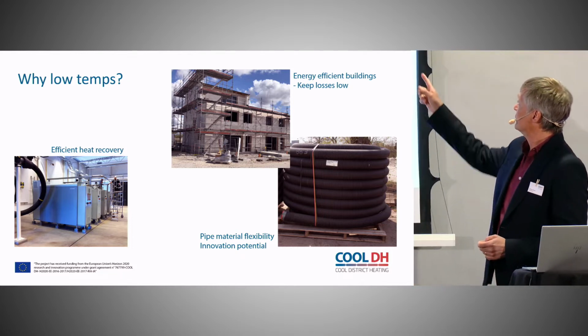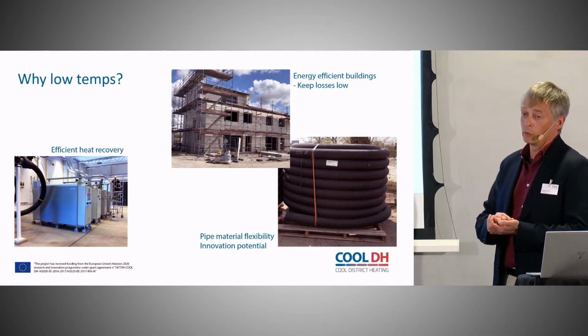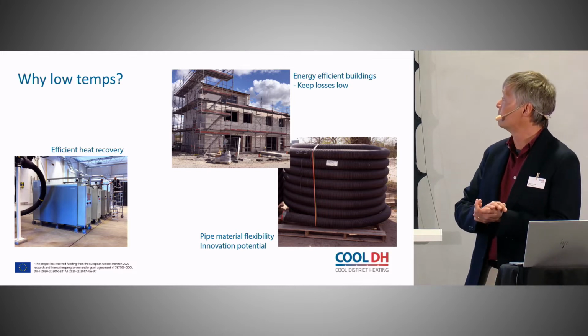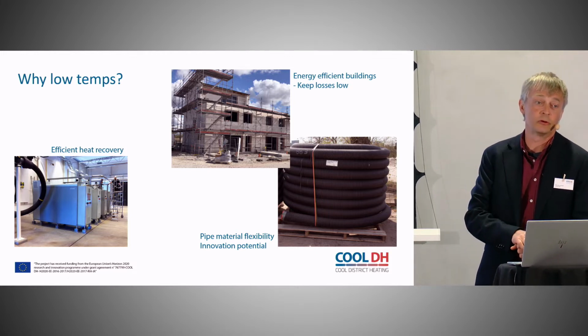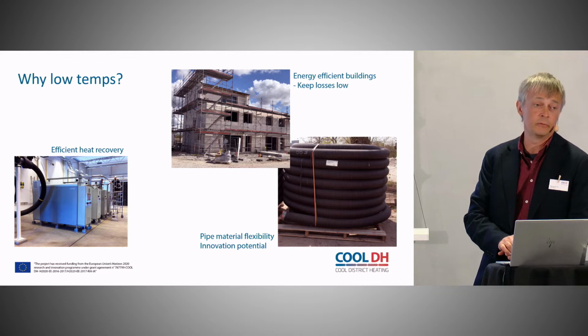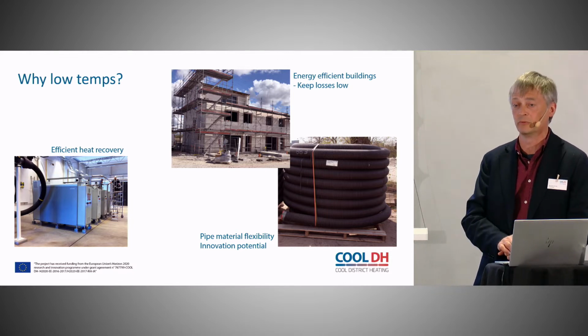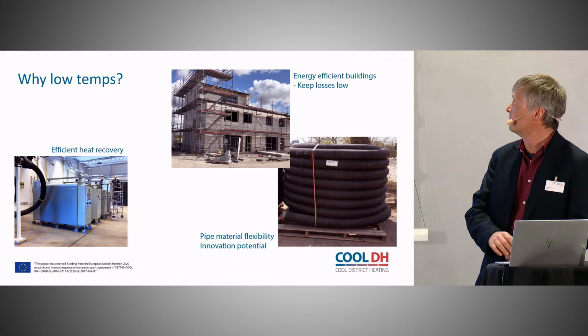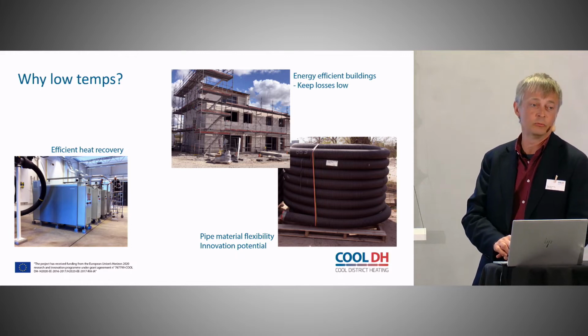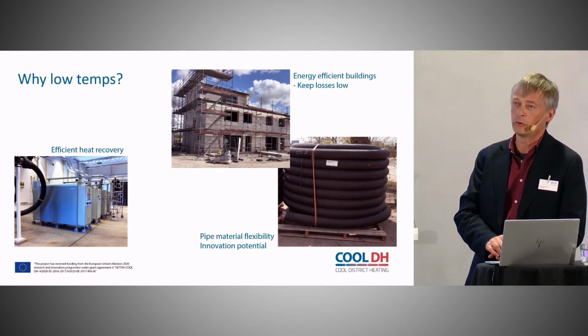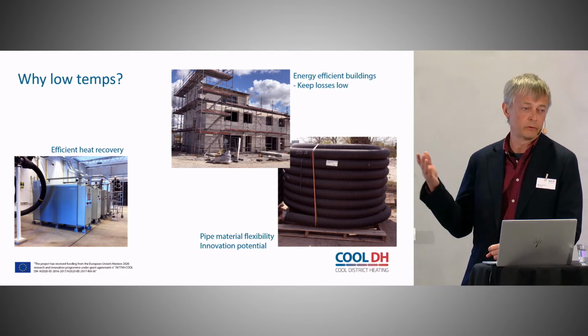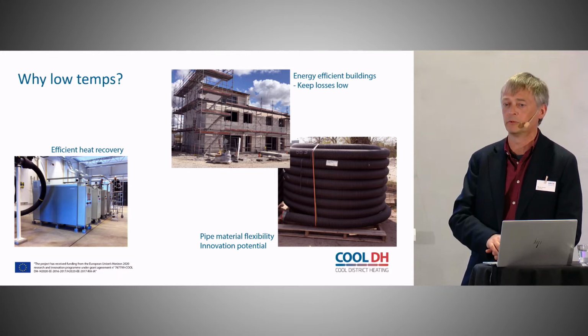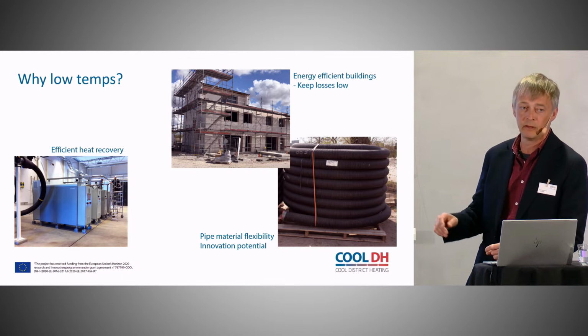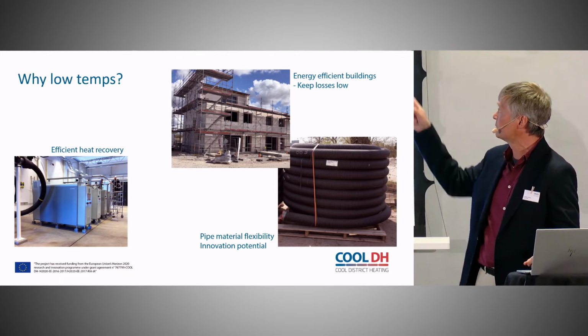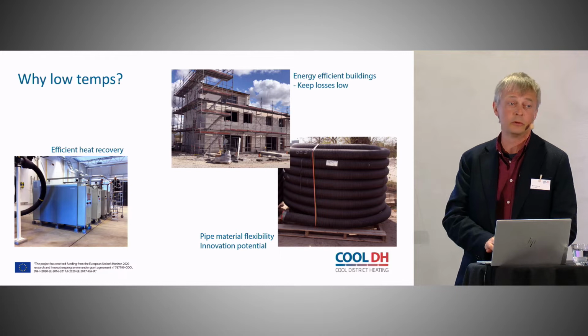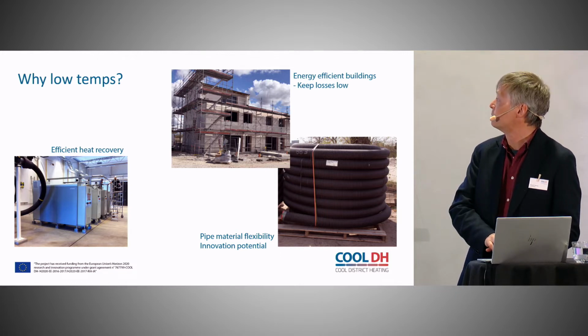And finally, we quickly realized that if we go for lower temperature, we can start using other materials. Normally, district heating pipes are built in steel, but here we found out we can use plastic. We were not satisfied with the pipes on the market at that time; they were not quite up to the standard we wanted. So we developed, within the Cool DH project and together with our partner Logstor, a new type of pipe.